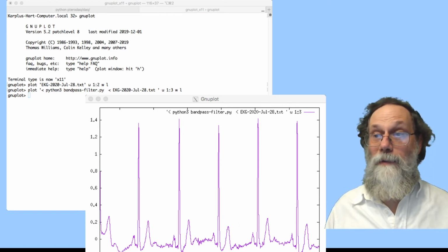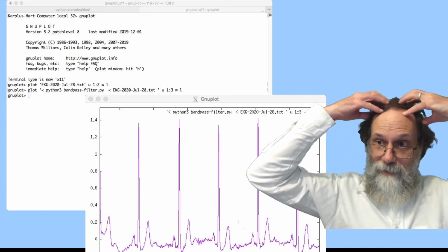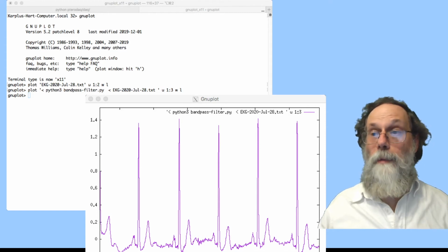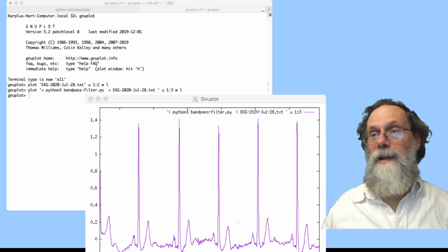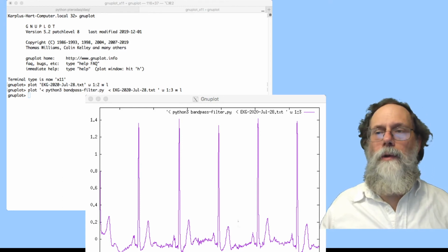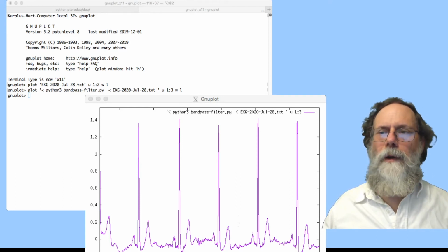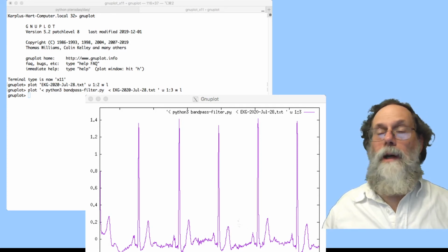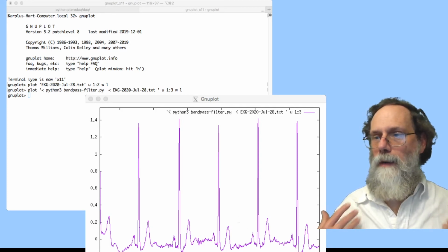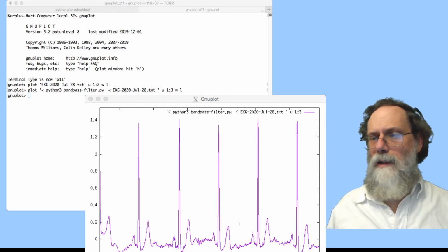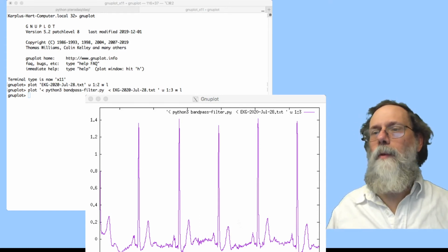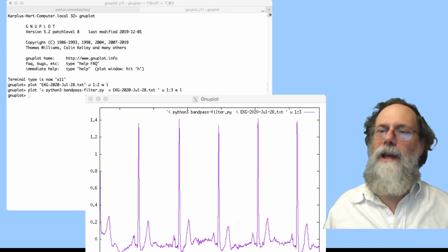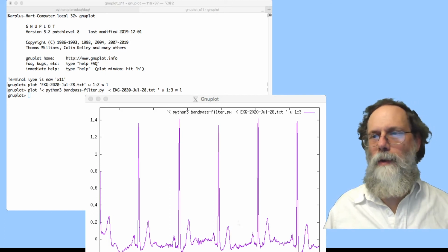And then if you want to gather very small data, you can get electrodes on the skull to measure neural behavior inside the skull. And those are electroencephalograms. Those are much more difficult because the signals are very, very small, and so you have to be much more careful about avoiding noise. Here, the signal that we've got from the heart is a millivolt or two. The ones from the brain are a few microvolts. So you need much higher gain and much better noise control if you're going to deal with those.